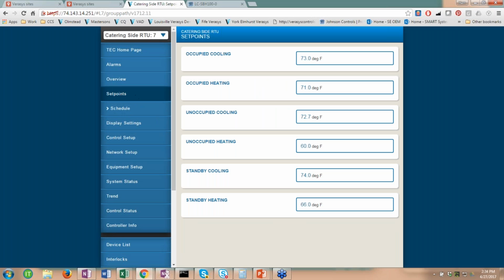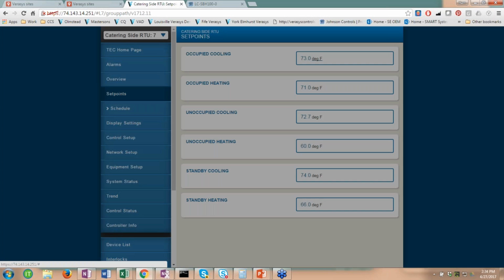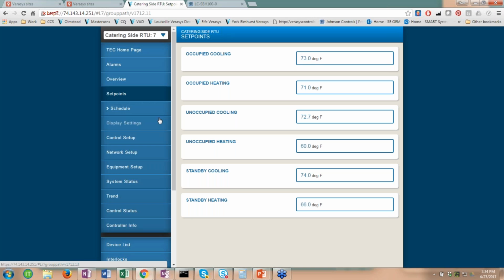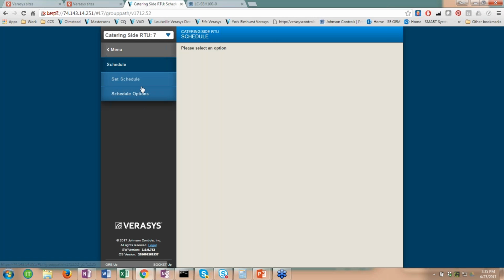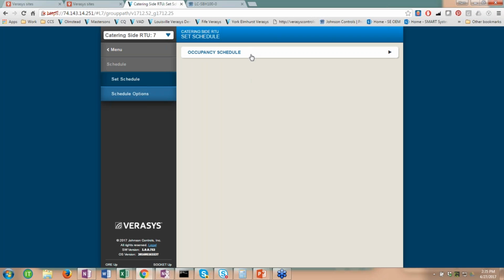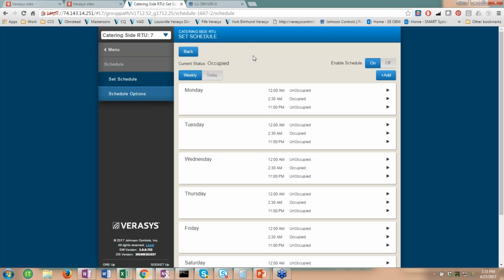So things like set points, these are the configuration parameters I was mentioning earlier. I could come in here and make the changes that are necessary. These would be my occupied cooling, occupied heating, unoccupied cooling, and unoccupied heating. I also have a built-in schedule that I could go in and set the schedules for every unit.